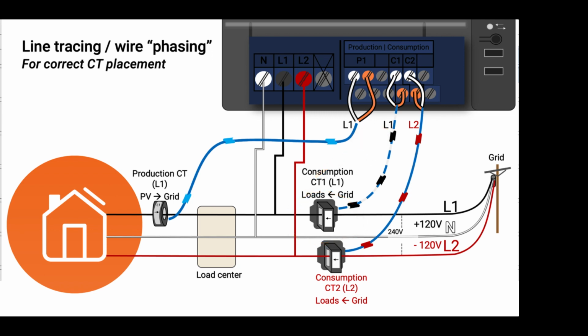So the power measurement is going to be correct for line 1 as we are measuring voltage and current from line 1 together. Line 2 is also aligned in its phase, with the line 2 grid power going into the line 2 terminal of the IQ gateway and the line 2 CT on the same line 2 grid line, with the CT connected into the CT2 connection at the IQ gateway. The problem we run into is when installers don't check to ensure that the wire the line 1 CT is on is actually the line 1 wire from the grid, and also the same line 1 at the IQ gateway, just in case wiring is crossed somewhere in the house or electrical panel. So you have to check that it goes all the way through. Checking phases is a critical best practice to ensuring metering is properly installed. Testing for phasing is covered in the CT Essentials online course, so check it out more there.